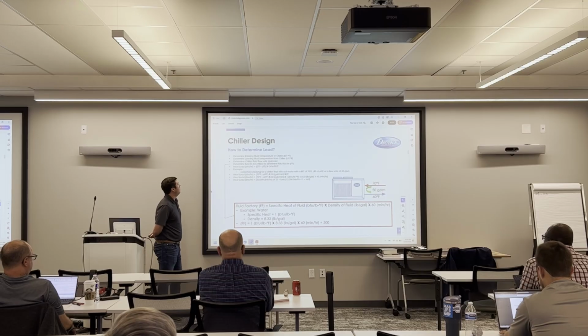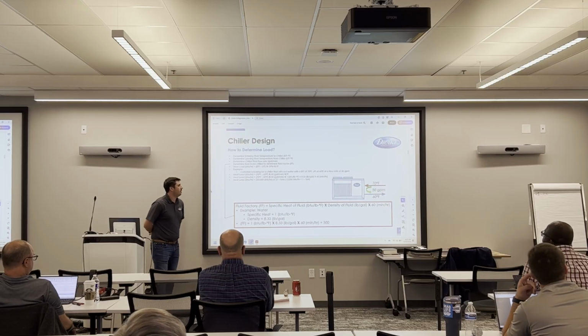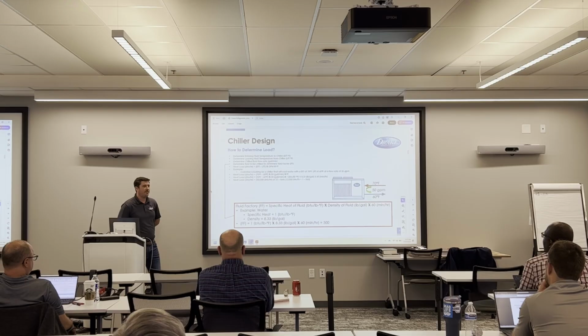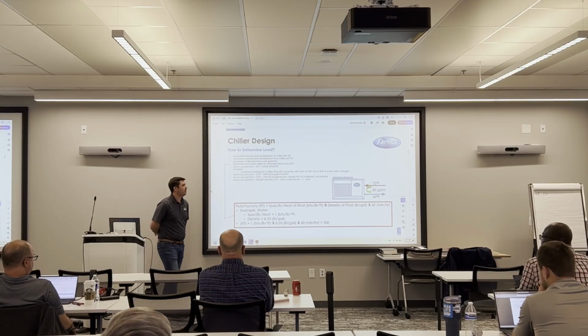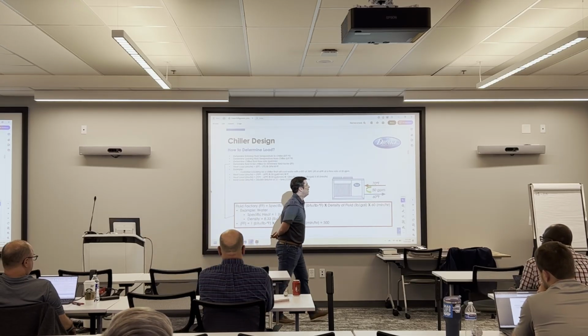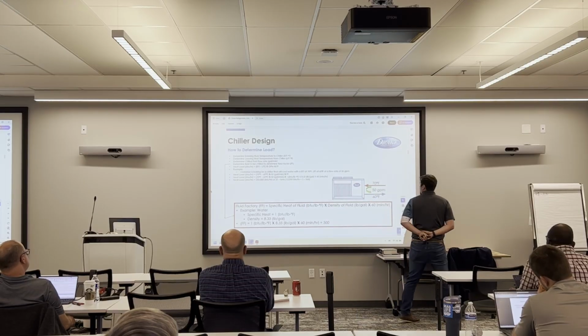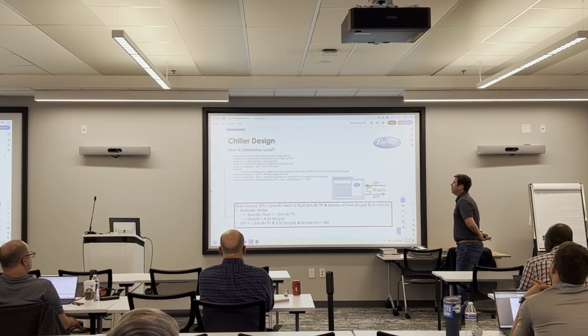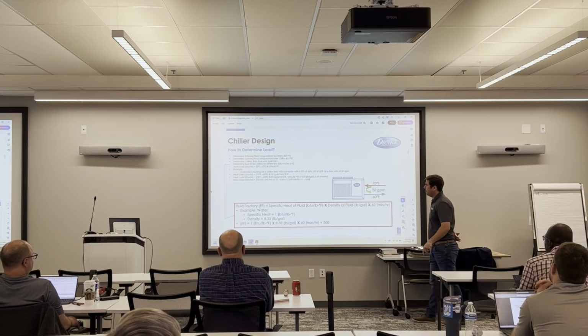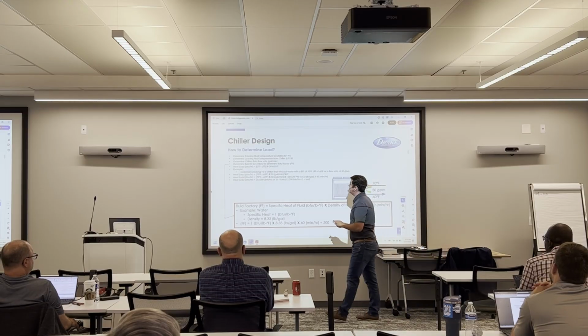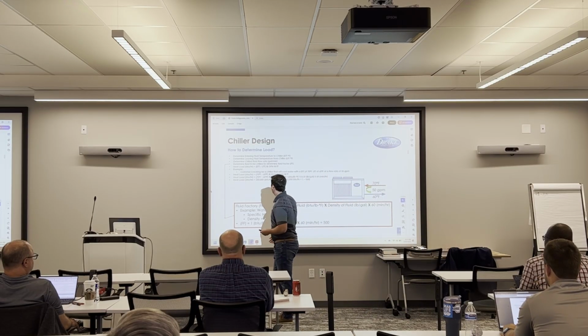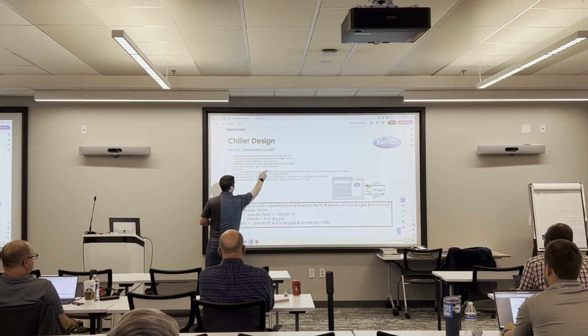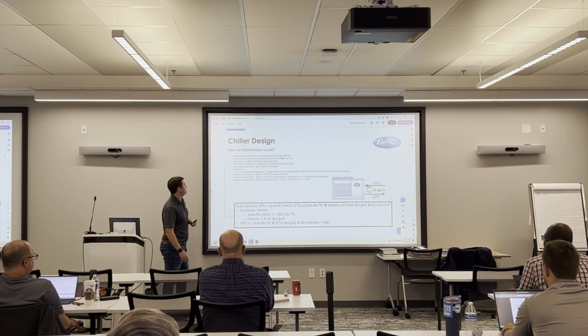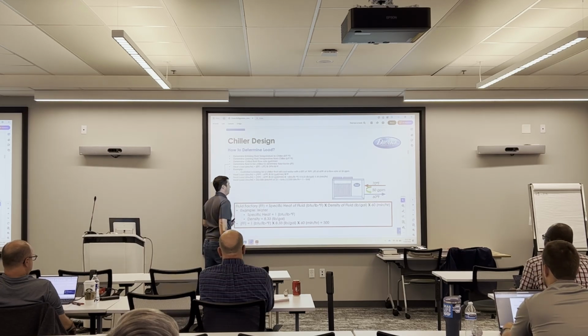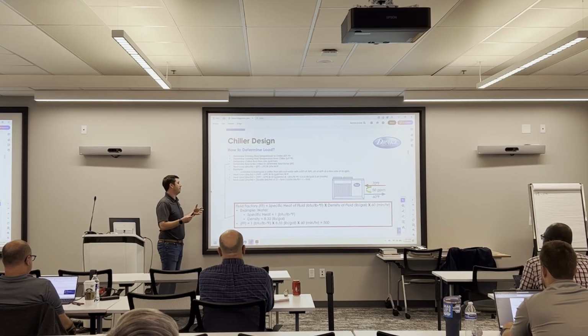All right, so we had the customer call in, and they say they need a chiller. The first thing we need to figure out is, well, what's the heat load for the chiller? And then once you figure out the heat load, you can figure out what size chiller you're going to need. So the way we go about quantifying load in the simplest form, we get an entering fluid temperature, a leaving fluid temperature, which is your temperature differential. We'll multiply that by flow rate. We do things in gallons per minute because we're Americans. And then we'll multiply what's called a fluid factor. So a fluid factor takes into account the properties of the fluid.